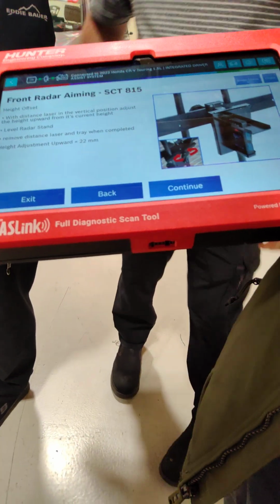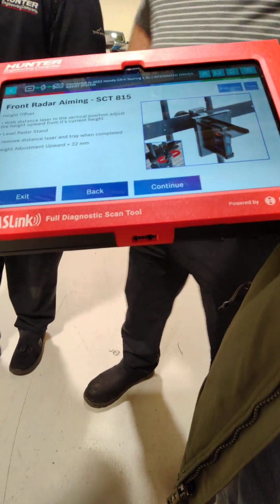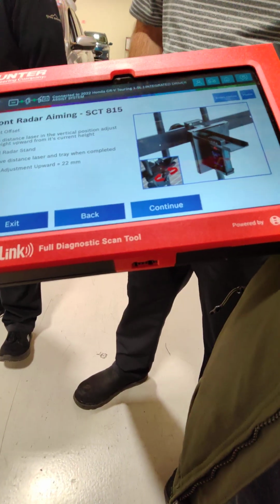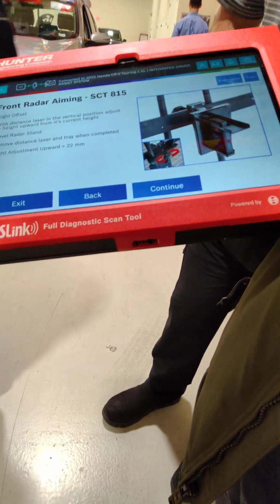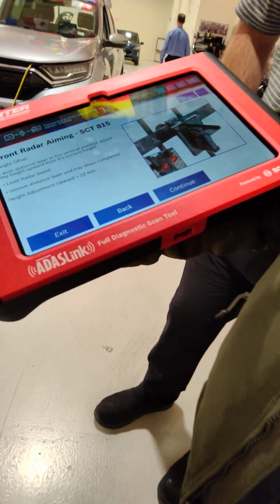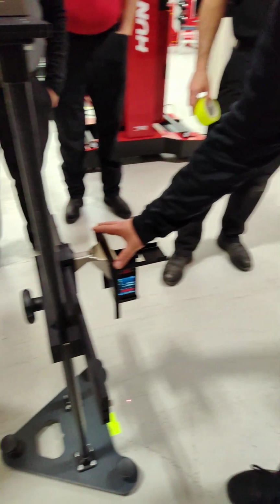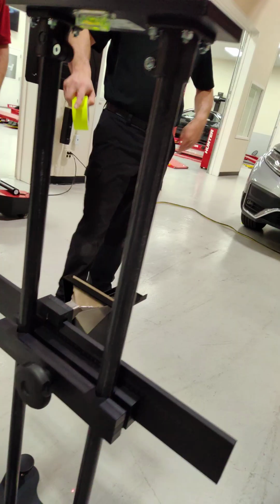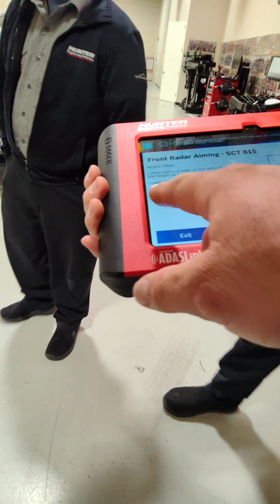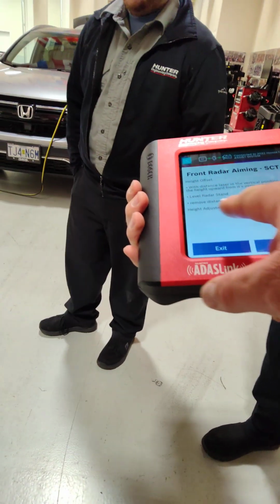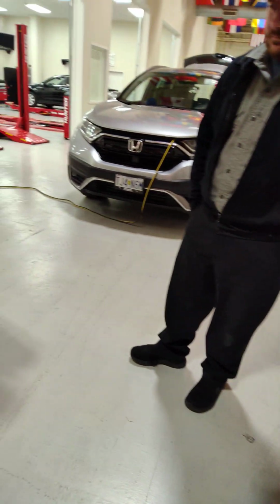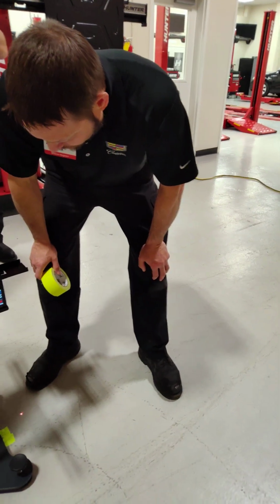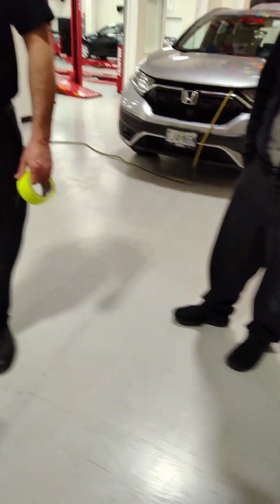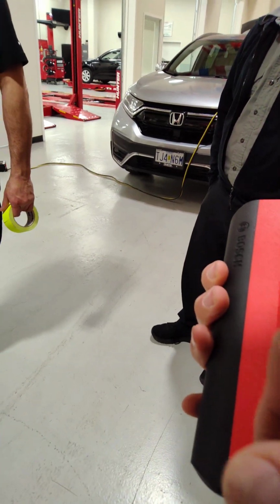I had a 50-50 shot. I mean, you were close. You were close. With distance laser in the vertical position, adjust the height upward from its current height to 22 millimeters. You have to level the radar stand first. So everything's still level. We took that off. Remove distance laser tray when complete. So it just needs to be 22 millimeters from the ground. Now we gotta adjust. 22 from the ground? Millimeters? It says height adjustment upward equals 22 mm.